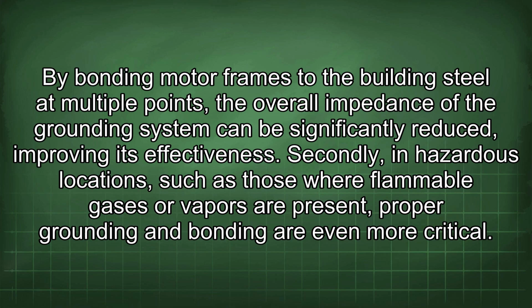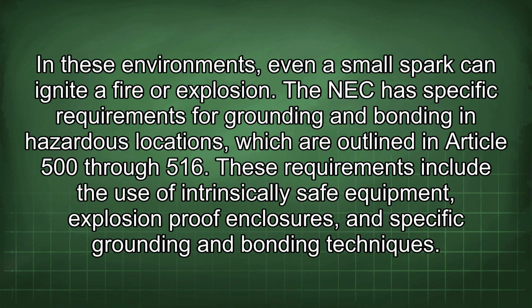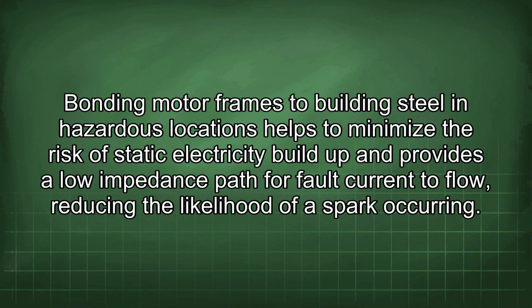Secondly, in hazardous locations, such as those where flammable gases or vapors are present, proper grounding and bonding are even more critical. In these environments, even a small spark can ignite a fire or explosion. The NEC has specific requirements for grounding and bonding in hazardous locations, which are outlined in Article 500 through 516. These requirements include the use of intrinsically safe equipment, explosion-proof enclosures, and specific grounding and bonding techniques. Bonding motor frames to building steel in hazardous locations helps to minimize the risk of static electricity buildup and provides a low impedance path for fault current to flow, reducing the likelihood of a spark occurring.